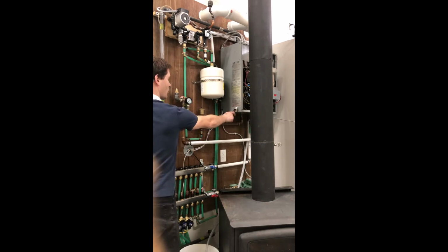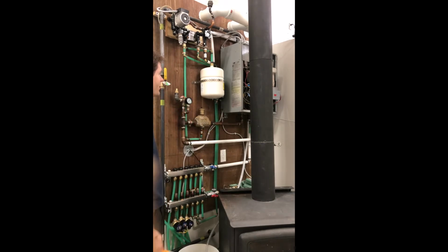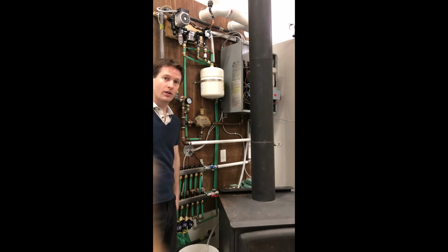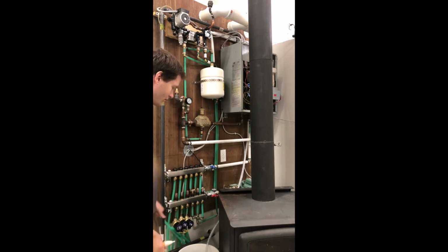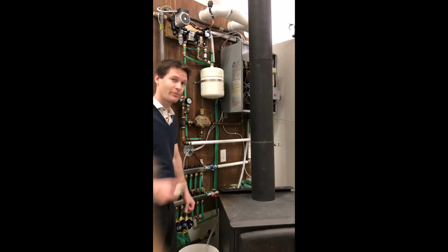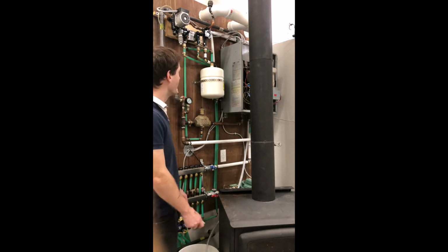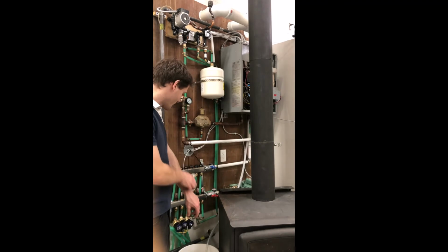So we've got our boiler over here, a 150 kBTU natural gas boiler. Natural gas line coming in here, we've got our shut-off, our union, and then the gas goes up into the top there. I've got 3-inch CPVC exhaust and intake piping — I just bored a hole through the wall. I destroyed one of my hole saw bits on the Hardie board siding, so if you've got Hardie board siding, prepare to buy a new hole saw bit. That stuff's hard as rocks.